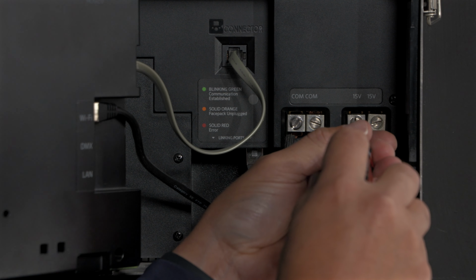We're now going to troubleshoot cloud mode. We go to Test. Verify that all tests run successfully and display. Currently, all network tests are failed. The controller will not connect to the Luxor cloud. To make sure that the network we are connecting to actually has AWS access, we need to select a different network. Confirm that it says connected to router. Then we go back to our test screen and make sure everything says OK.